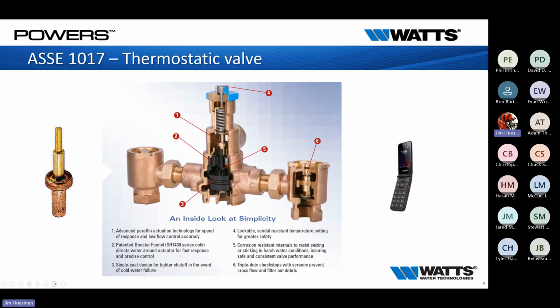I'm not talking about dirty water or water that doesn't taste good, but if we get extremely hard water, what happens is we get a large scale buildup on top of this element. Once we have a large calcium buildup, if hot water comes up to try to touch this and expand it, it takes forever, so our water gets cold in the building. Eventually the hot water heats through the calcium and finally heats the element, allowing it to expand and push down, letting more hot water run through. But when cold water comes over to hit that element, it takes a while to work through that calcium base to finally hit the element and allow it to contract.